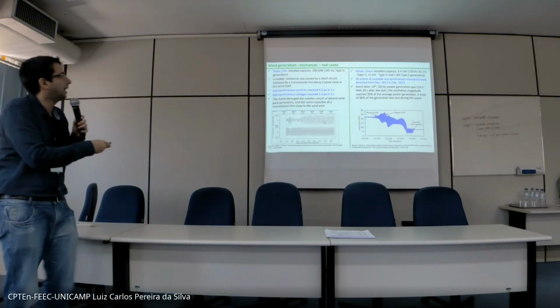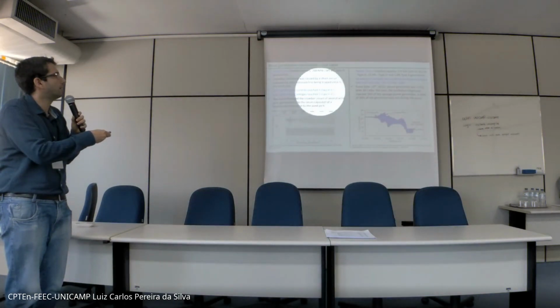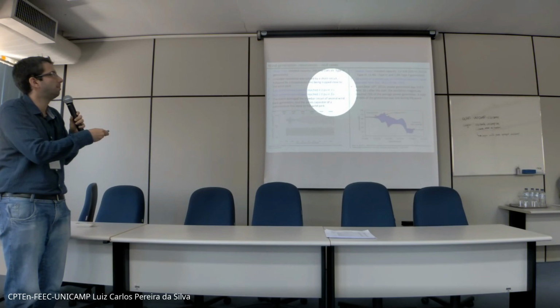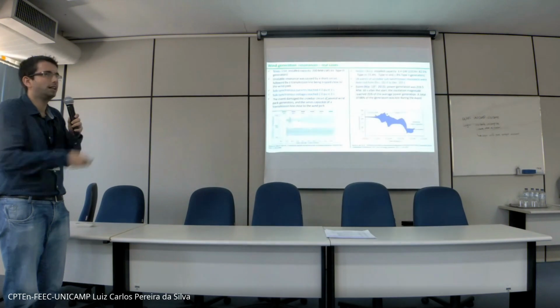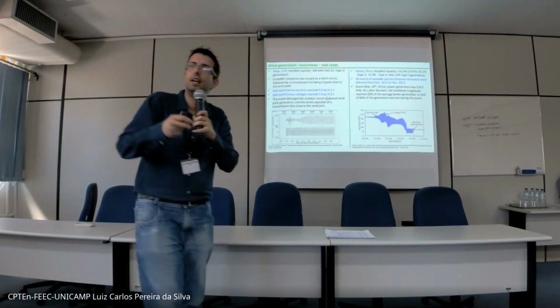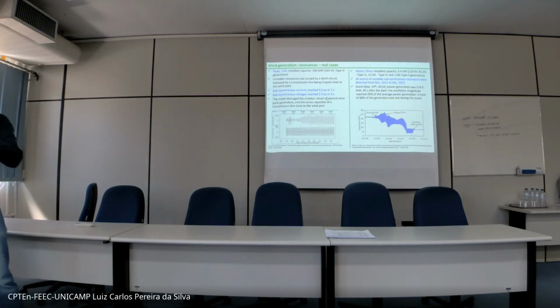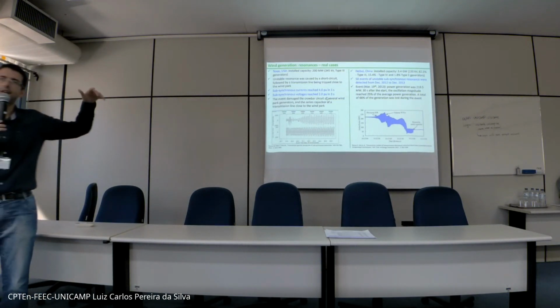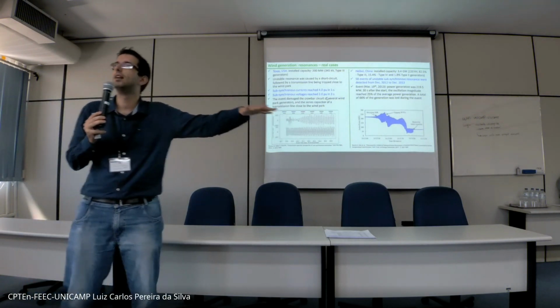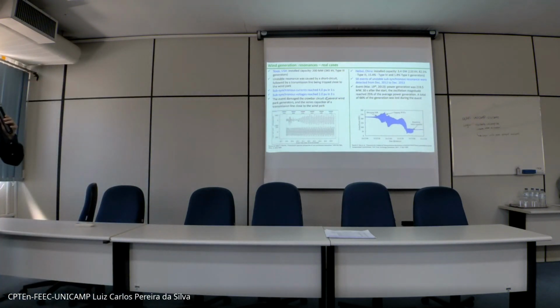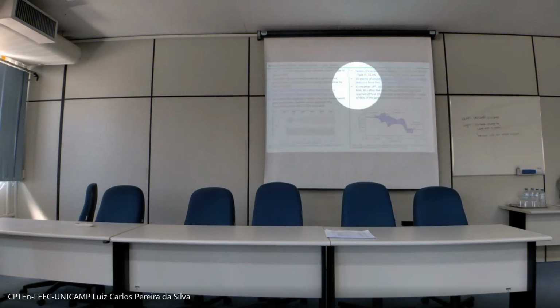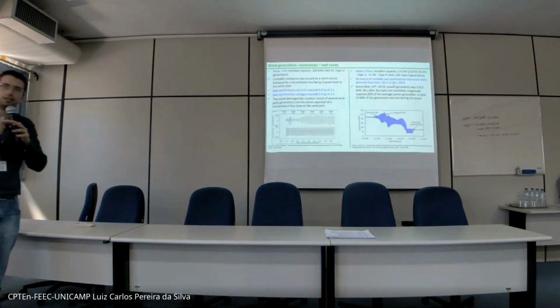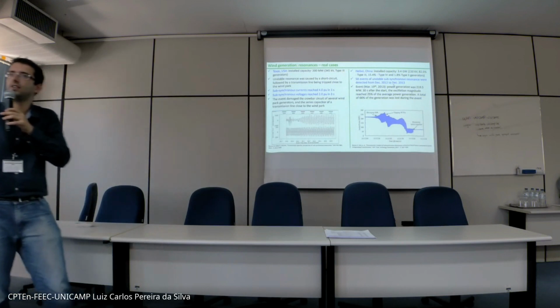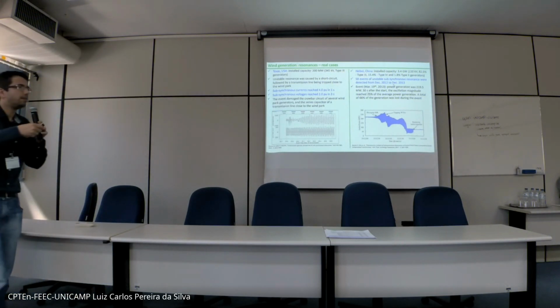In the US in 2009, a wind park's subsynchronous currents reached 4 per unit in less than a second, and subsynchronous voltages reached 2 per unit in less than 3 seconds - very fast, very big events. Unstable oscillations caused damage to the wind generators and capacitor banks around them. In China, a wind park complex experienced 58 events of unstable subsynchronous resonance in 2012-2013, over a one year span - that's more than one event per week. So this is really happening.